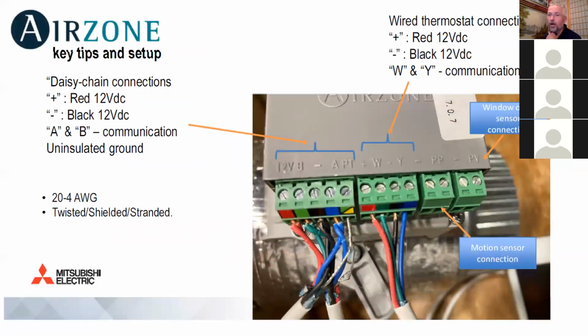On the individual modules for the zones, there are these connectors. The one with 5 connectors, this is the daisy chain. You can see there are 2 sets of wires coming in here as part of that daisy chain. They all just get wired together. And then right next to it, these 4 connectors, the plus, minus, W, and Y. This is the set of wires that would go to your wired thermostat, your blue face thermostat.